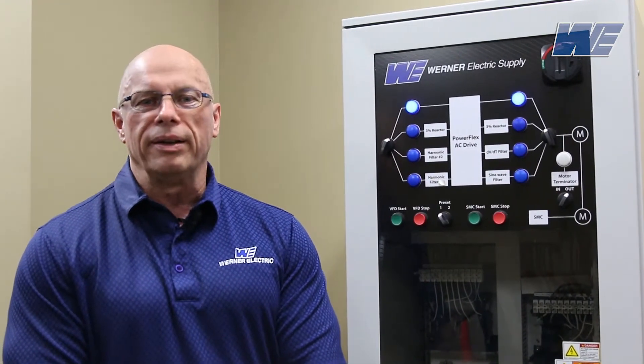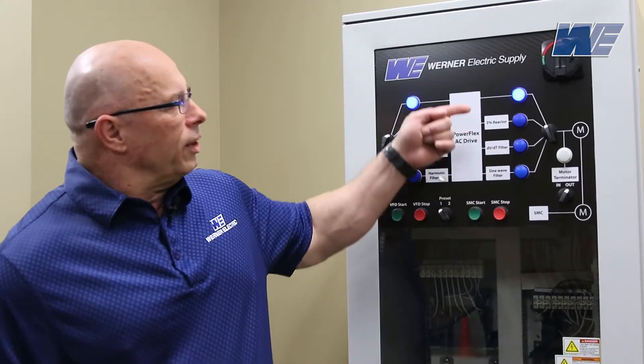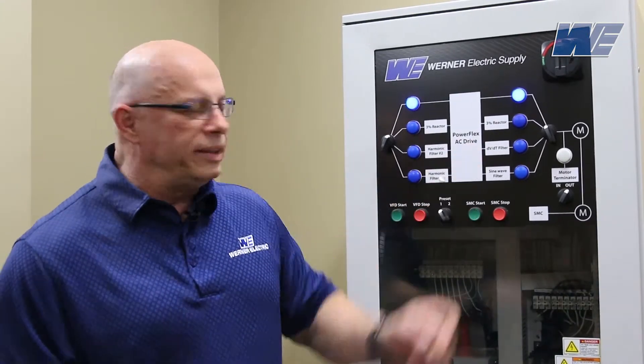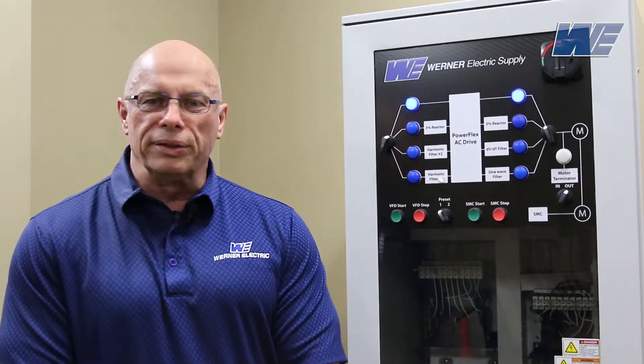We have a pulse width modulated 3 horsepower PowerFlex VFD. We have 500 feet of cable between the drive and the motor. We're going to have our oscilloscope terminated at the motor. We're going to look at the output without a filter, then add a 3% output reactor, add a dv/dt filter, and also look at a sine wave filter.